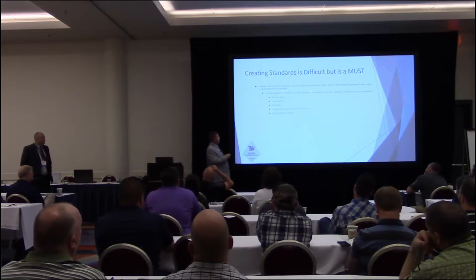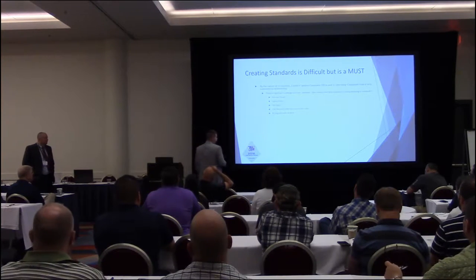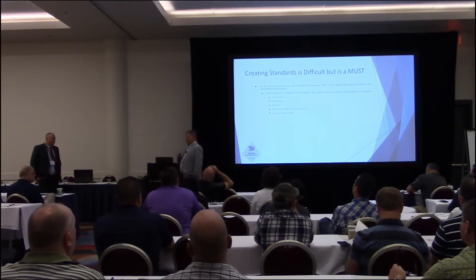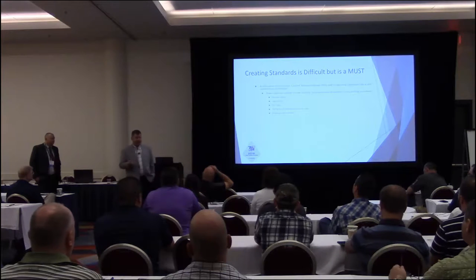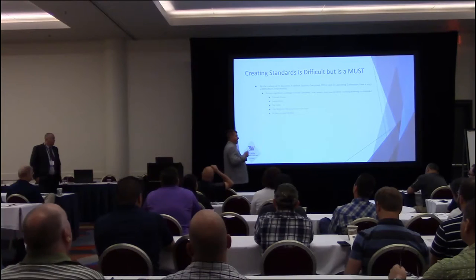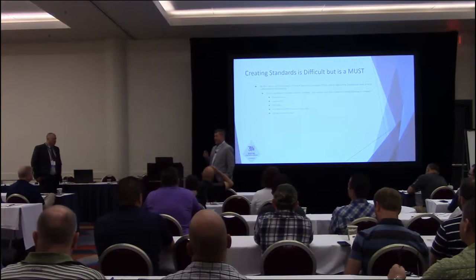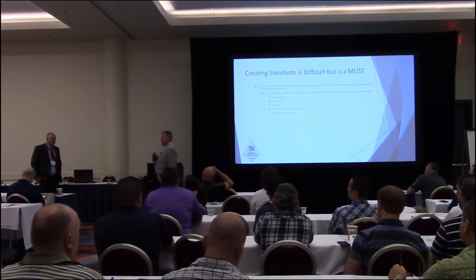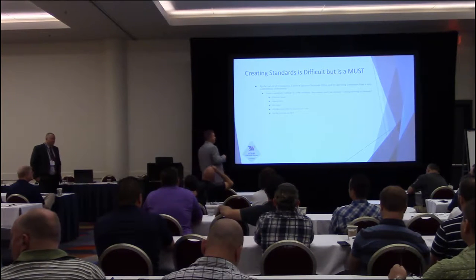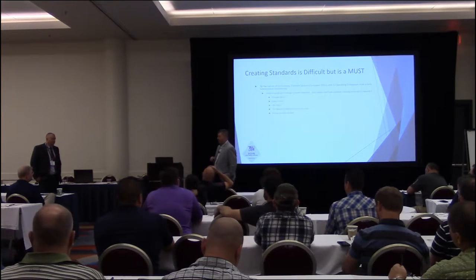It's actually right here. So I have to keep looking back at my monitor to make sure where we're at. So when we talk about pressure classes, right, the way we're going to fabricate ductwork, are we bumping up the gauge to take out the stiffener? Or are we leaving it the way that it is to leave the stiffener in, right? What are all of these little things that, for you sheet metal guys, you understand what I'm talking about? How do we want to interpret that SMACNA manual to build ductwork the most efficient way possible, but also meet all the criteria we needed to meet, right? Okay?